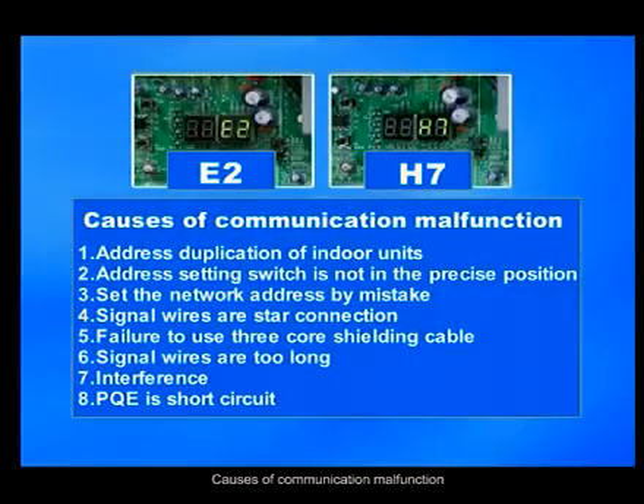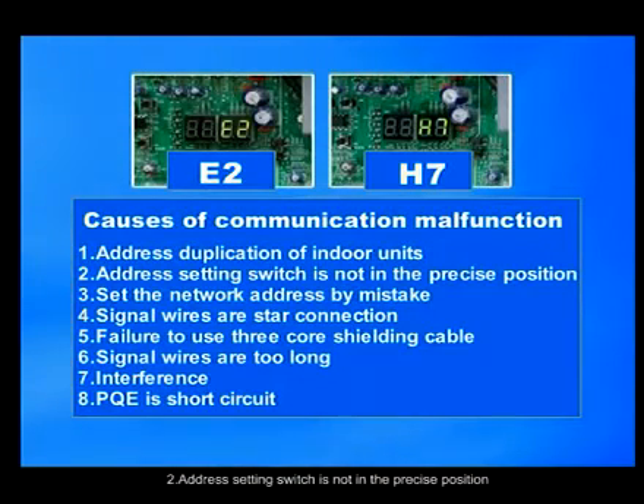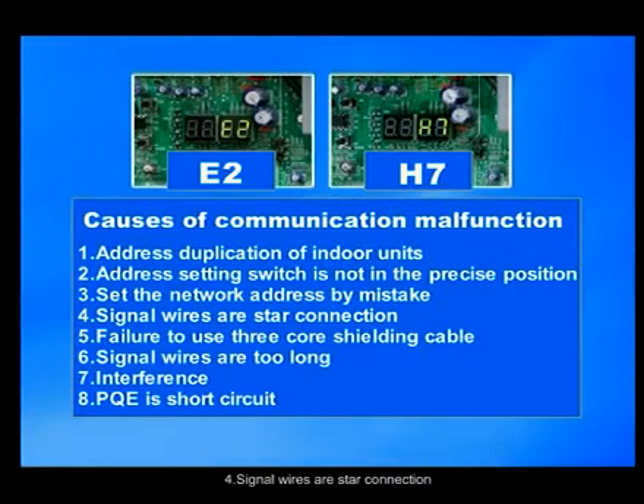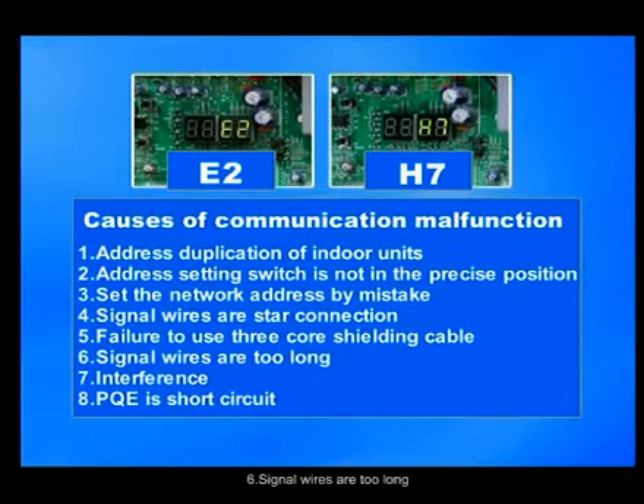Causes of communication malfunction. 1. Address duplication of indoor units. 2. Address setting switch is not in the precise position. 3. Set the network address by mistake. 4. Signal wires are star connection. 5. Failure to use 3-core shielding cable. 6. Signal wires are too long. 7. Interference. 8. PQE is short circuit.